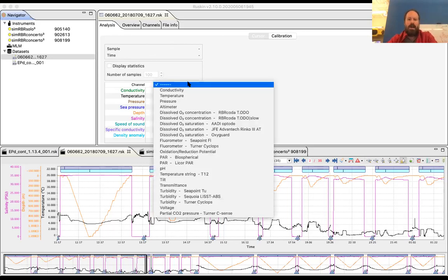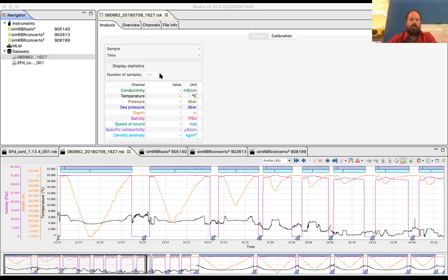And maybe we'd want to add an optode to that, or a turbidity sensor from, let's say, Seapoint, that kind of thing. So we can do that here. And we can also add a variety of options, such as the sample rate, the maximum sample rate that the instrument can do. In our quartz family, which are all based on Paroscientific quartz pressure gauges, you can simulate the quartz Q, the quartz BPR, or the new BPR0, which implements the A0A technique for getting rid of drift.